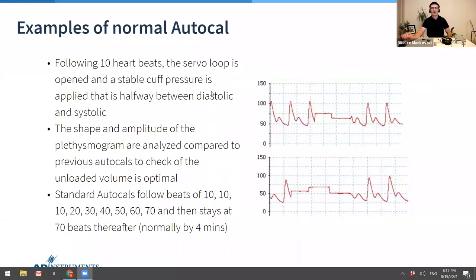Some examples of good Autocal you can see here. So over time, as I mentioned, following 10 heartbeats, the servo loop system is opened and a stable pressure is applied that is halfway between systolic and diastolic. At this point, the servo control center within the NIBP examines the shape and the amplitude of the wave, and then it will adjust for what the unloaded volume is optimally at, and then it continues with the blood pressure reading at a more accurate estimation. So when it first starts off, it starts off with 10 beats, Autocal, 10 beats, Autocal, 10 beats, Autocal, then 20, et cetera. Normally this takes about 4 minutes. So I'd say about 5 minutes in, you're going to get the best readings.